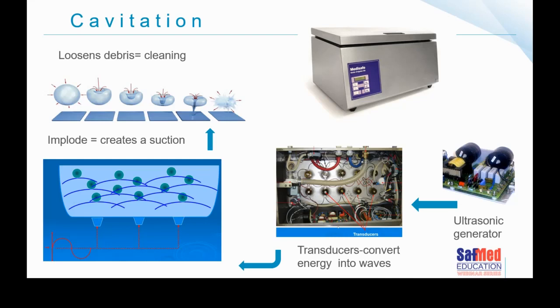All of the sound waves in the water, and those of you that work in CSSD have heard it often, create that shh sound. The sound waves in the water create millions of little bubbles. The bubbles implode, which means they collapse inside of themselves. And as they implode, it creates a little bit of a suction. That suction effect is what loosens all of the debris and creates the cleaning action. The process is called cavitation.